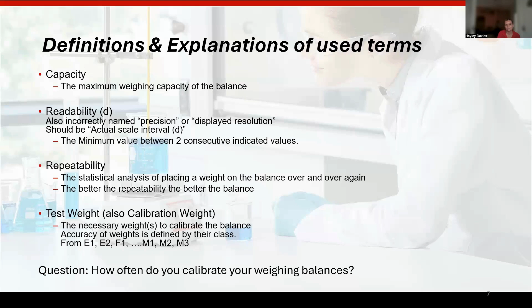So with the calibration, it is a way of adjusting the measuring instrument to a reference point, and the reference point here would be the calibration weight. You are adjusting the balance to a known weight, a known value.